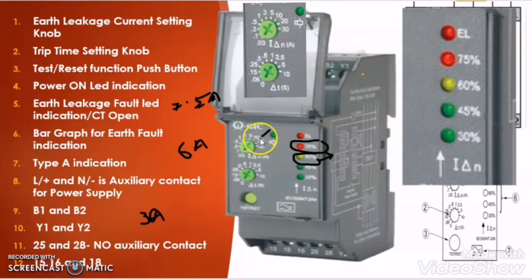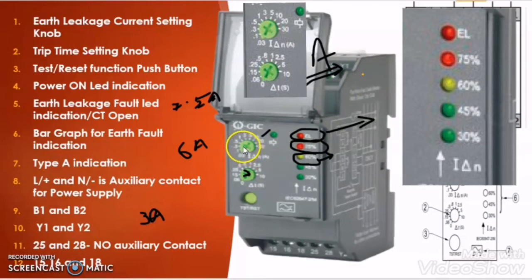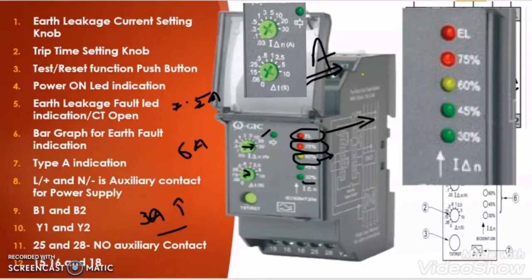If the earth leakage relay is experiencing an earth fault current of 10A, it will wait for 5 seconds if the time dial is set to 5 seconds. After 5 seconds, if the earth fault current is still 10A, the relay will trip and the trip indication bulb will glow. Note: if the dial is set at 30A instead of 10A, the 30% LED will not glow when sensing 3A — because 30% of 30A is 9A, not 3A. So the percentages are always based on the set earth leakage current value.